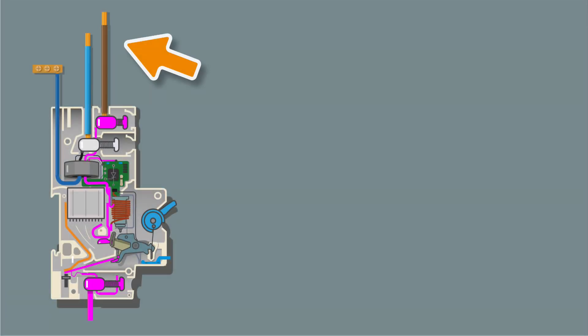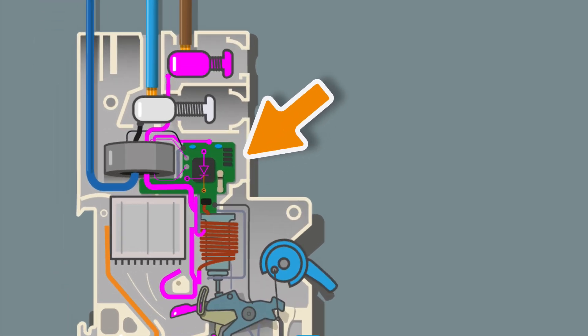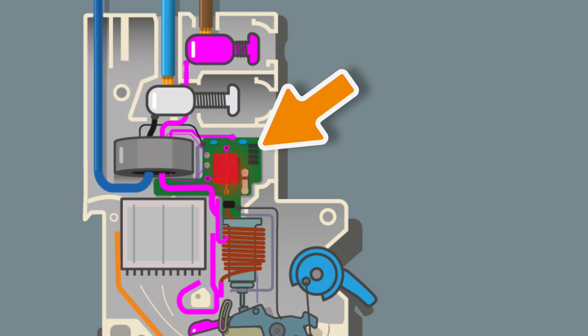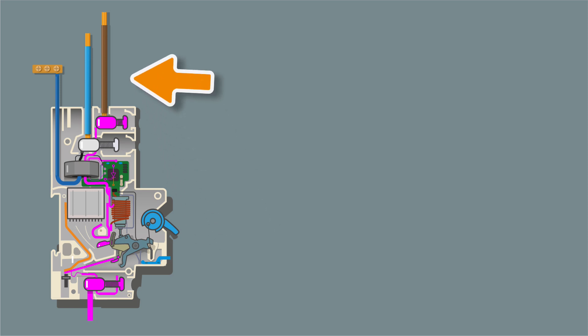Now add the second source of power from the solar inverter. We get: working, sensing, operating — and then overloading. You'll notice that the RCD has operated, but power hasn't stopped at the moving contact. We've got the second supply feeding from the top of the RCBO, still energizing the circuit board and causing the electronic components to fail.